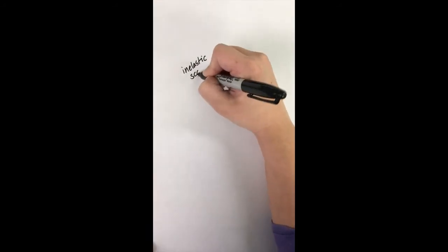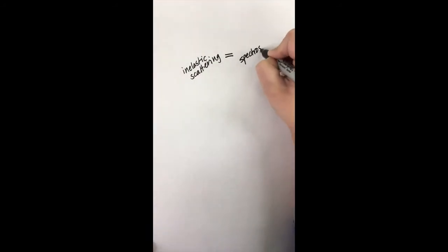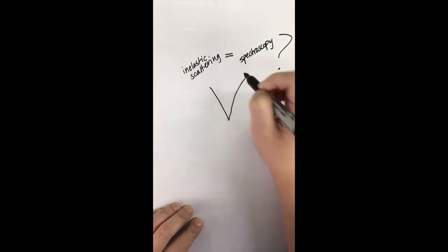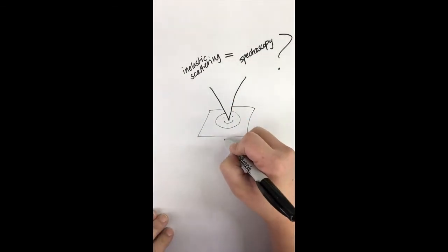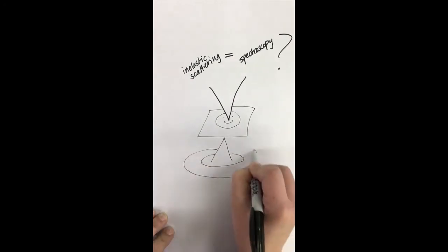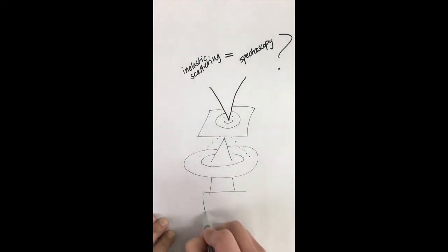So how do we turn inelastic scattering into useful information to be used for spectroscopy? Well, when the electron beam hits and exits the sample, these electrons can then be funneled into a special electron spectrometer that spreads them based on energy. This can then be funneled into a detector, and this detector produces a spectrum based on the energy differences in the electron.